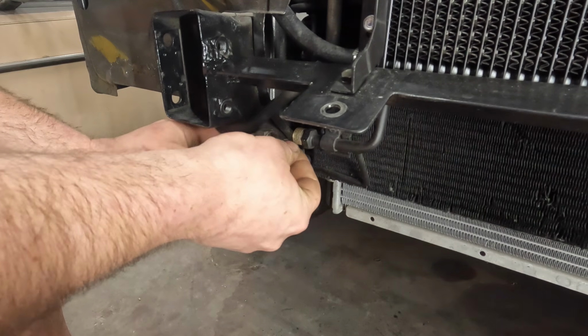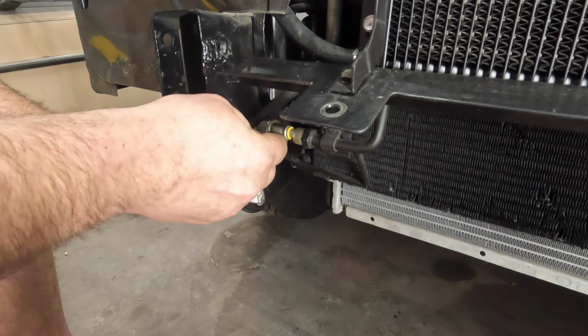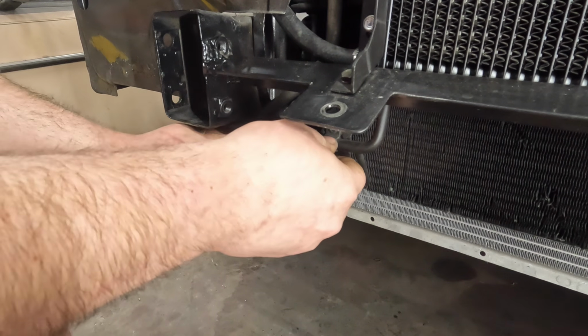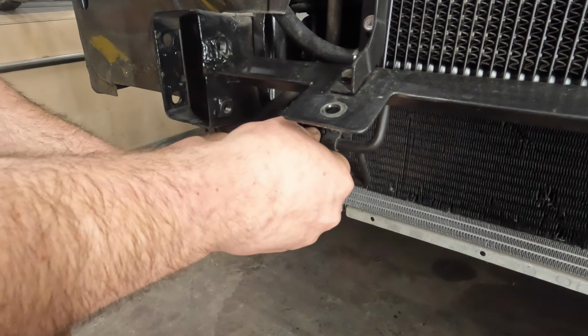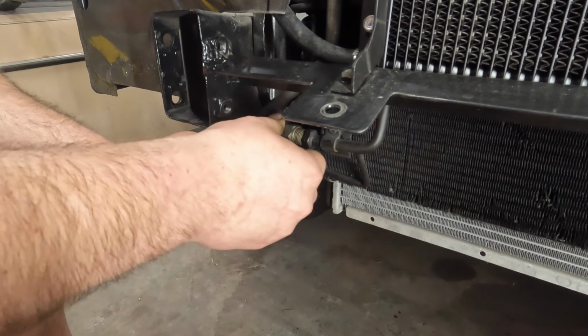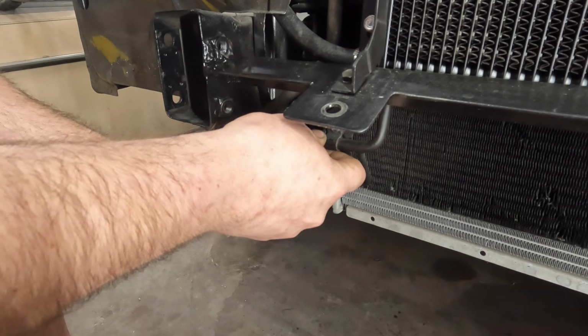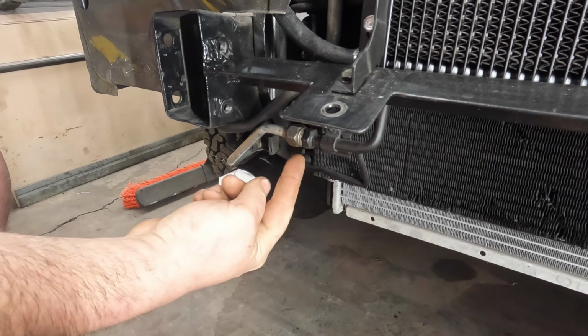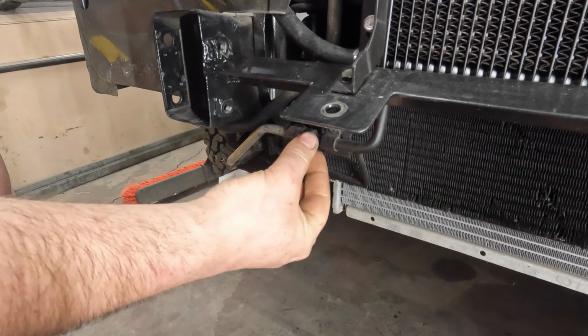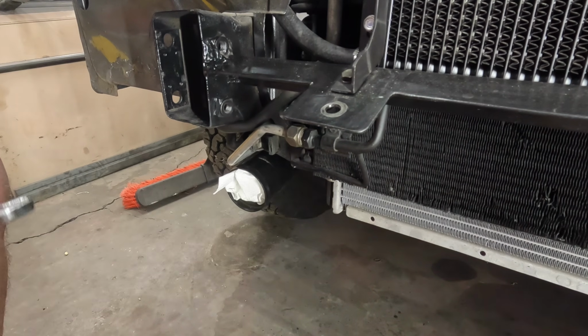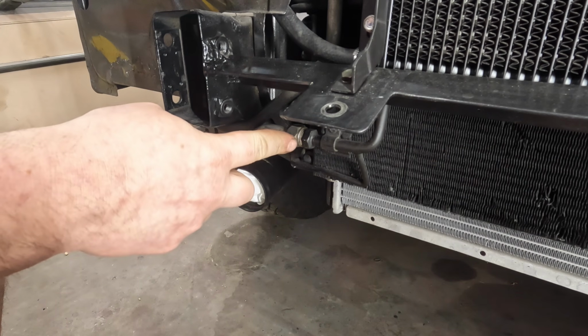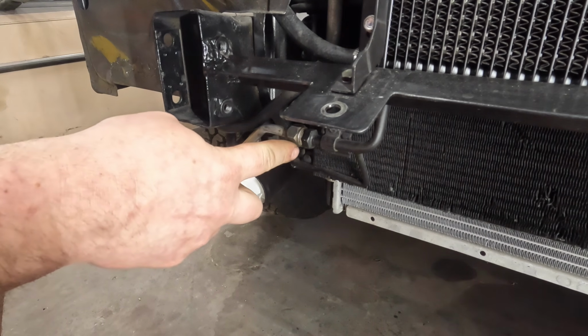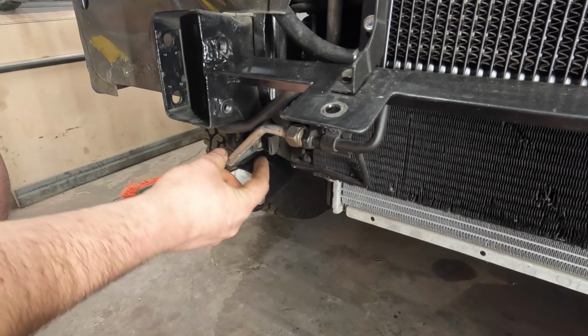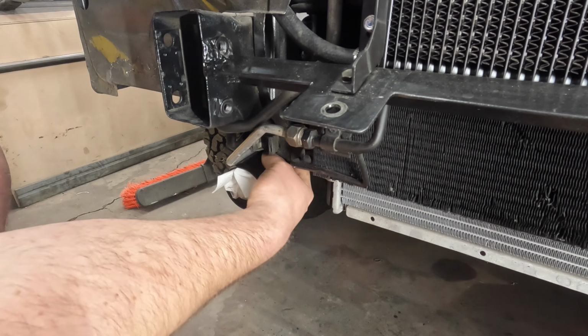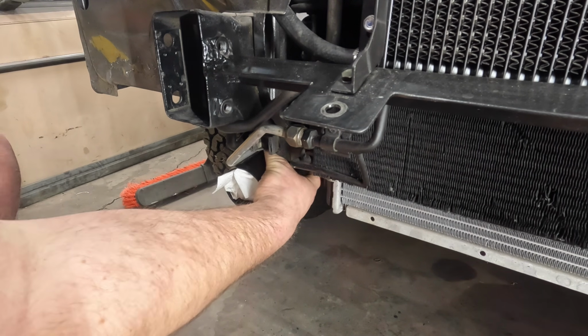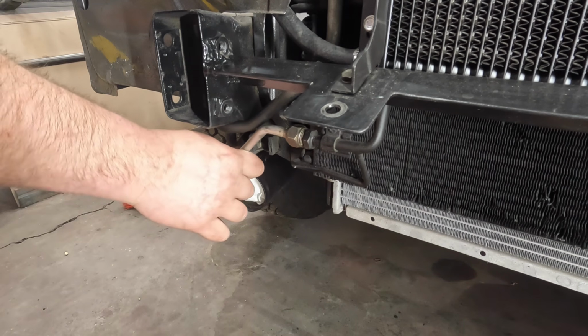When you're putting together these O-ring fittings, keep in mind it is not a compression fitting like a flare fitting. The O-ring is doing all the work, so they don't need to be ridiculously tight. And of course, putting them together is the easy part. If you've ever taken this type of fitting apart after 30 or 40 years, you know it can be a little dangerous and painful. Also going to have to get a little creative with the routing down in this area, what with the intercooler pipe, but we'll get to that.